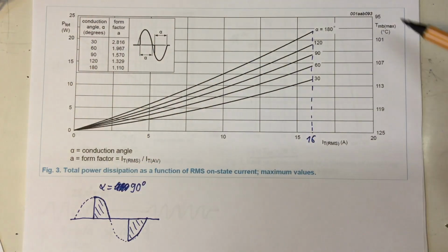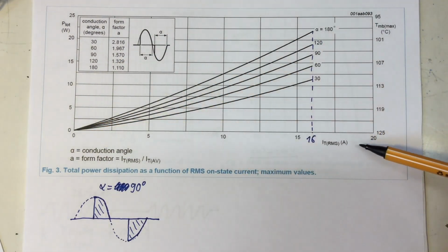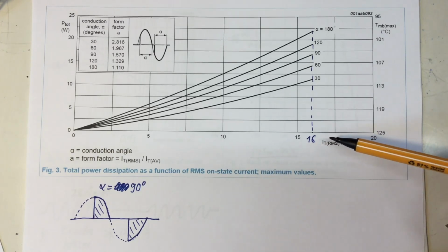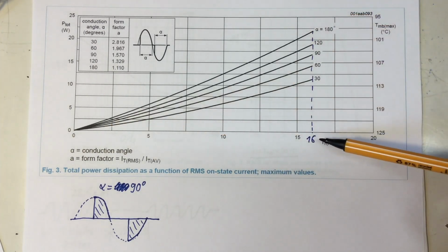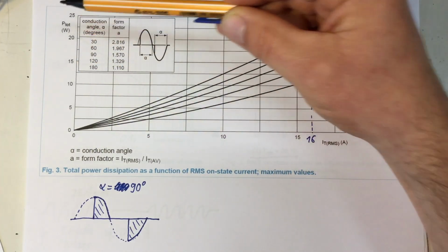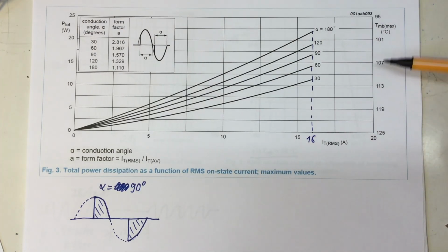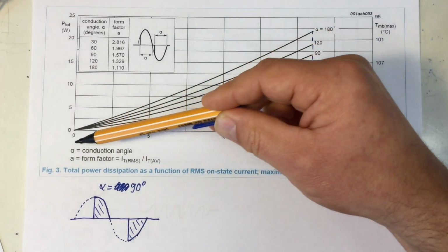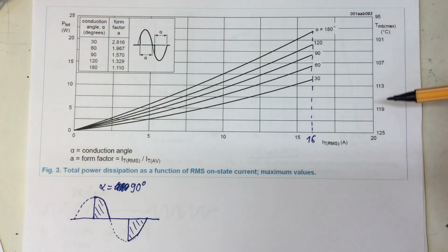The third figure is a bit more complex. At the bottom we have the RMS current going through the terminals, and all the curves end at the maximum allowed 16 amps. Here we have the power dissipation caused by that current, between 0 and 25 watts. On this side we have the related maximum allowed mounting base temperature, and this scale is upside down: 95 degrees C at the top and 125 at the bottom, which makes sense since the more power you dissipate, the colder your mounting base has to be.